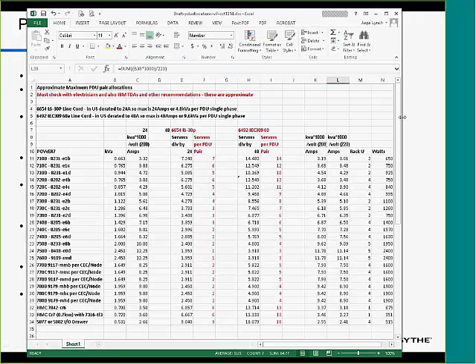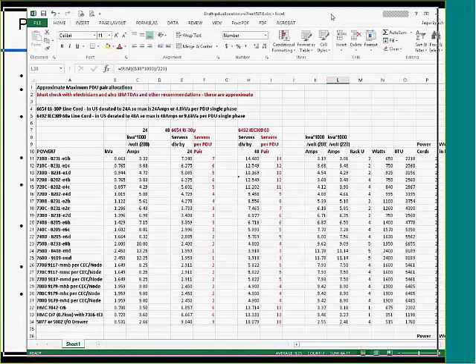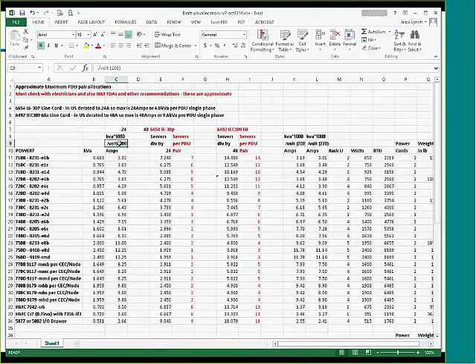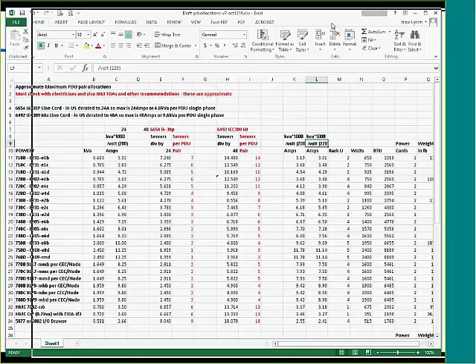So if I show you my spreadsheet that I use, let me grab that. In the spreadsheet, I track the numbers. I calculate amps depending on whether it's 200 volts, 208 volts, or 220 volts. And you can see that they're quite different. It ranges from 3.01 to 3.32 depending on the actual voltage. So you do need to know the voltage, or you can just simply say, I'll use the one that's the highest. So maybe I'll use the 200 volt number for my calculations because I know I'm never going to exceed that. But if you know that your power is 208 or 220, then use the real number.